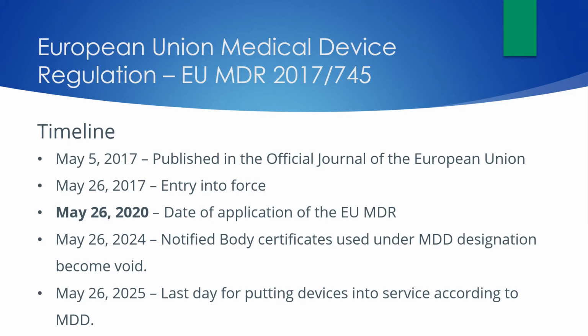Prior to this date, there have been some concerns expressed by the US to the European Union. In July 2019, the US asked the European Union to delay implementing the EU MDR by 3 years due to the lack of approved notified bodies. Minimally, the US asked the European Union to allow for legacy products that are currently deemed safe to be sold on the market until 2024, and for notified bodies to prioritize devices that need new certification over those being recertified.